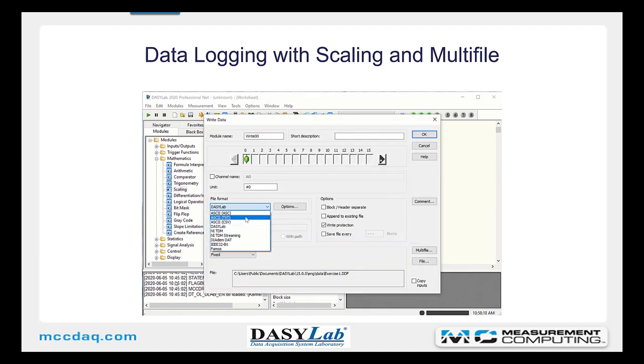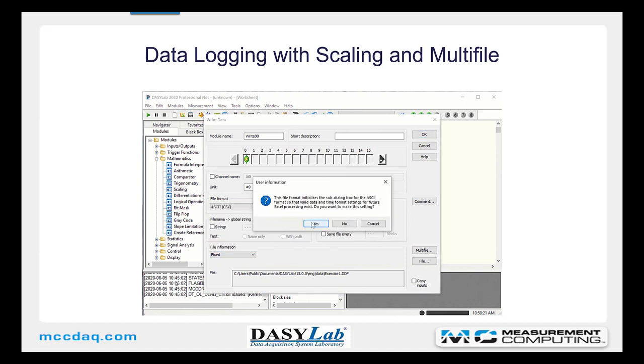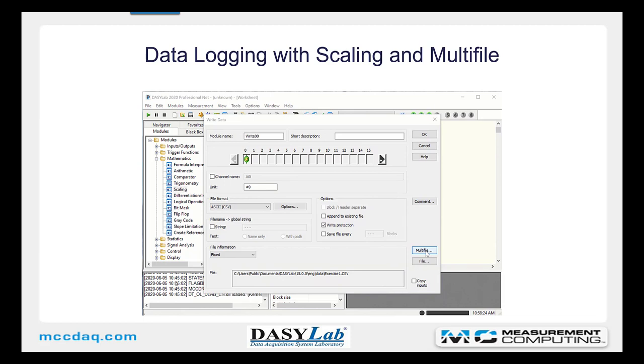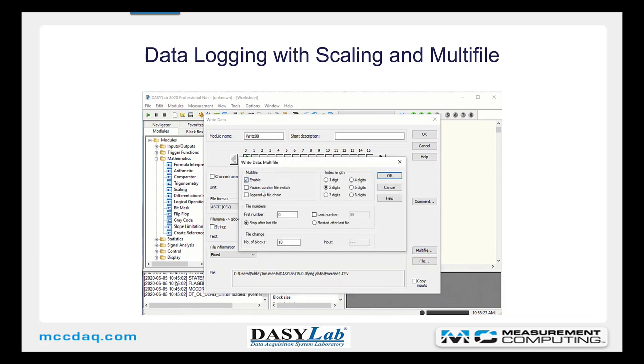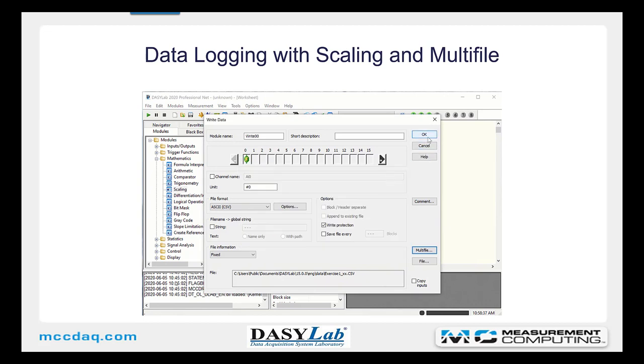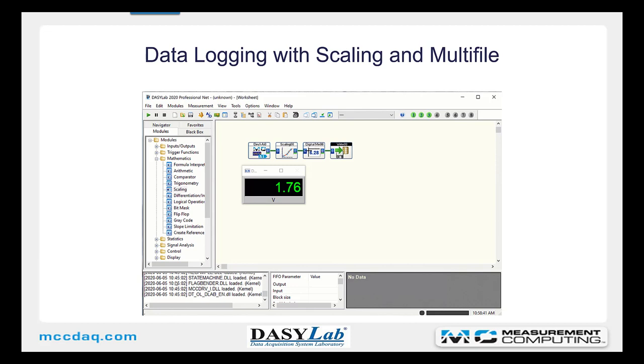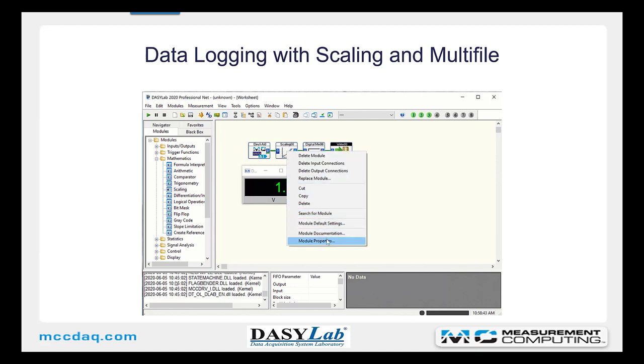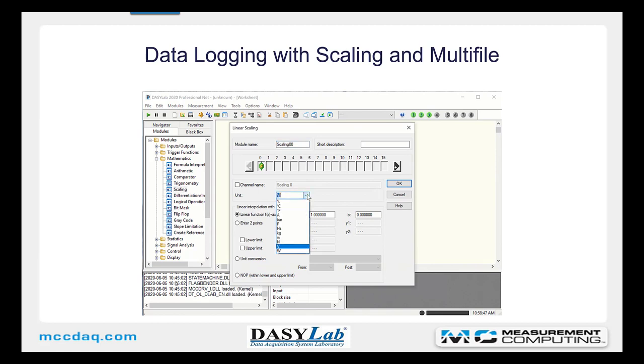Reconfigure the write module to change it to a CSV file — there's always a warning message, just click yes. Configure multi-file by enabling it, appending to the file chain, and changing the number of blocks to zero so that it only creates a new file when you hit the start button. Click OK, then go to the scaling module to configure scaling. Open its properties. I'm going to do volts to psi — psi isn't on the list so I have to type that in. I'll use two-point scaling where at five volts input I have 10 psi of pressure. Click OK.